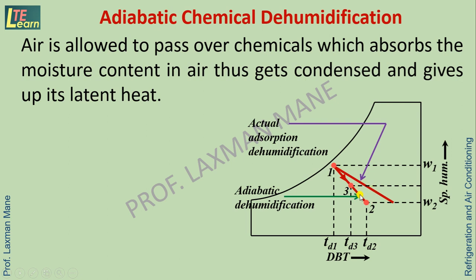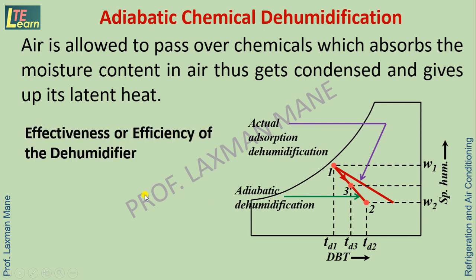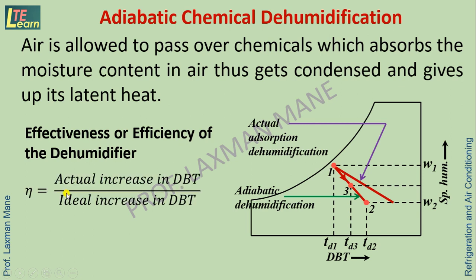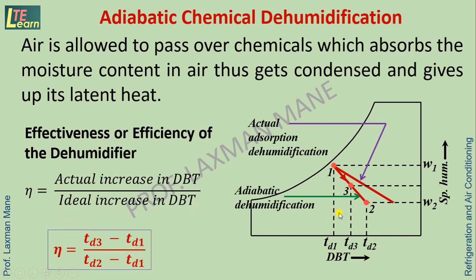The effectiveness or efficiency of the dehumidifier is the ratio of actual increase in dry bulb temperature to the ideal increase in dry bulb temperature. Actual increase in dry bulb temperature is Td3 − Td1, and ideal increase is Td2 − Td1. So efficiency = (Td3 − Td1) / (Td2 − Td1).